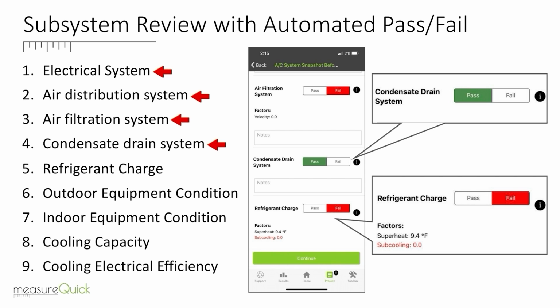Some things like your condensate drain, you're gonna have to put those in if they're subjective. Refrigerant charge, we're looking at superheat, we're looking at subcooling, we're looking at your high and low side pressure, your heat drivers. Outdoor equipment condition, indoor equipment condition, again, subjective, anything that would affect your cooling capacity and efficiency. So we actually run an analysis on that and do a pass-fail on those, completely automated.